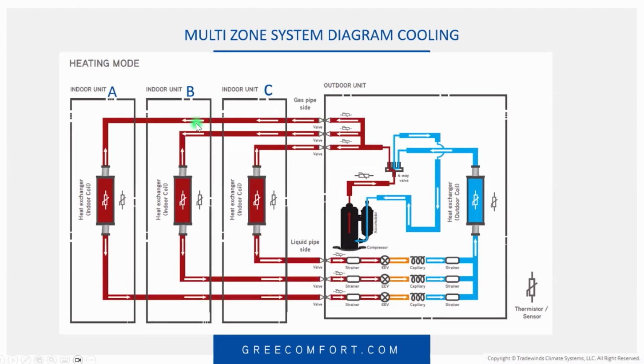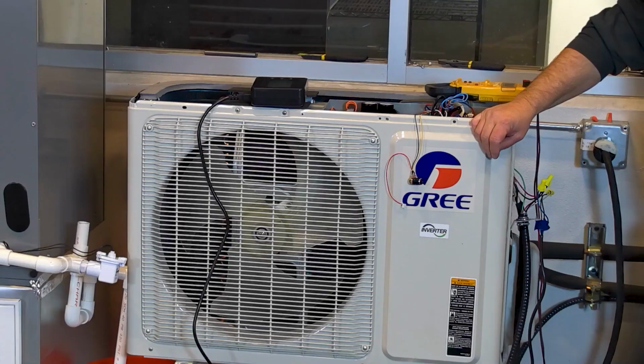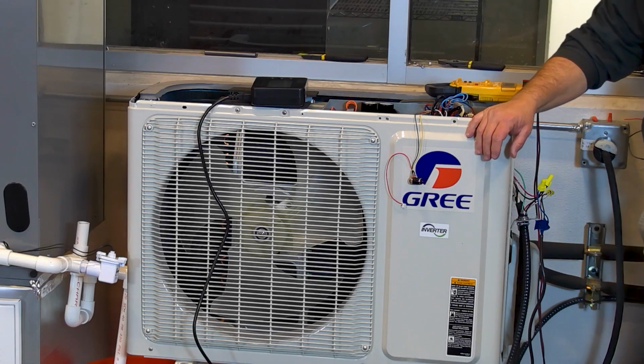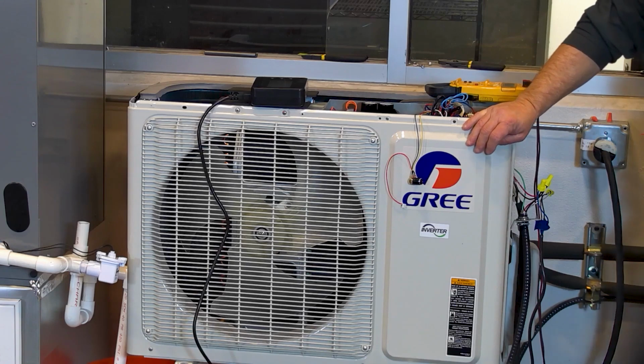So basically heating mode is the same thing. I'm not going to sit here and go through the flow for the whole thing. I think you guys are getting my whole point of what I'm trying to talk about here. So we've got a single zone mini split here. We've got our service tool. Some things to talk about with the single zone service tool, and this is what we're going to demonstrate. The single zone service tool can be used as a data logger. In other words, not really a data logger, but to see data in real time while the machine is running. Okay? Basically, this tool is your eyes and your ears into the system.